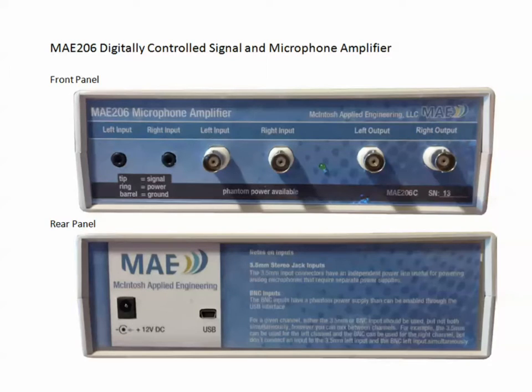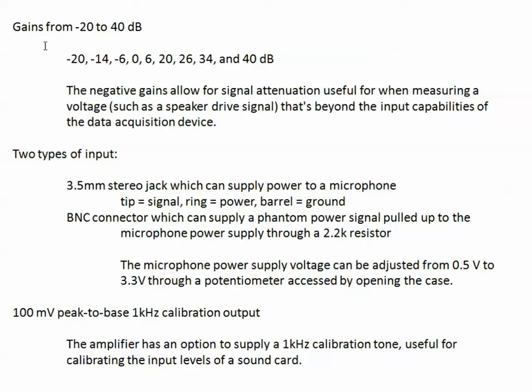Here's a close-up of the front and back panels on the microphone. The gains that the microphone can support on both the left and right channel are from minus 20 dB to positive 40 dB. The minus 20 is useful if you have, for instance, an 8 ohm speaker that's rated at 20 watts and you're playing a high crest factor signal into it, such as speech, you can get very high voltages in that situation. If your sound card is limited to just 5 or 10 volts and you're getting 40 volts across that speaker, you'd clip the inputs. So this minus 20 dB pad is very useful for those situations.